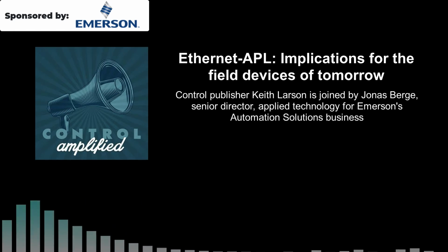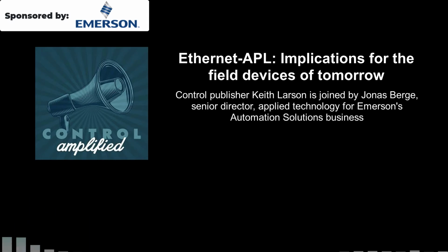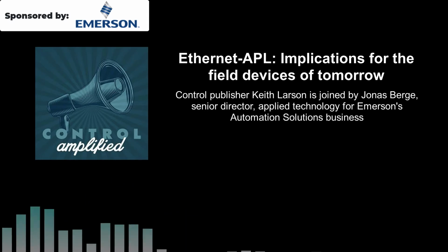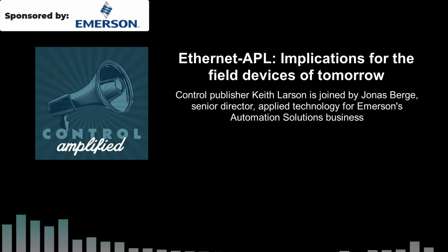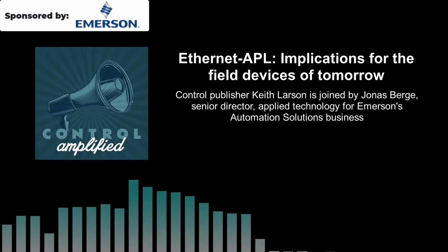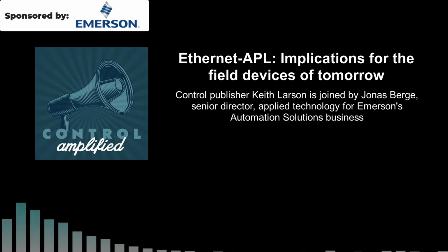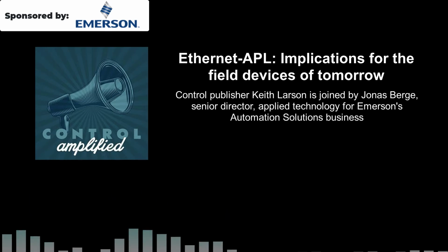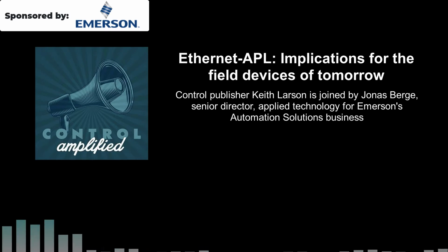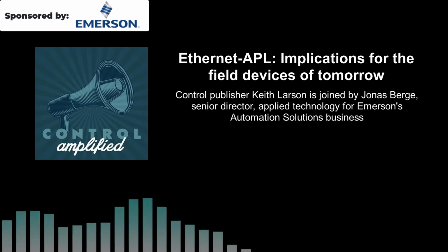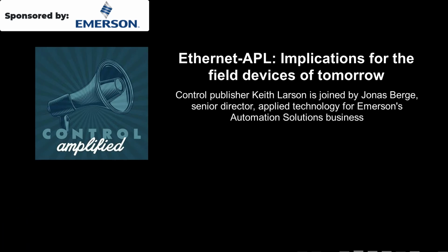Emerson, known for its Coriolis meter, benefits from APL's power and bandwidth, which allows it to be more sensitive, because you can energize the sensor and the tubes as they vibrate. Larger sizes today need a lot of power and have to be separately powered to get that sensitivity and accuracy. But with APL, you can get sufficient power over the same two wires, so you can have two-wire devices that are more accurate and available in larger sizes. This is a great example of what APL enables, and the same applies to MagFlow meters, which also need to energize the flow tube.